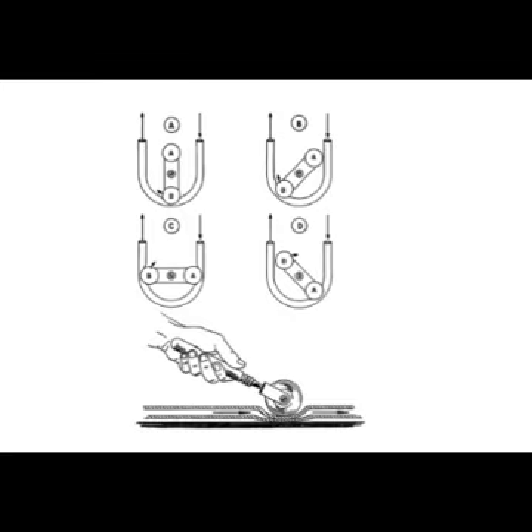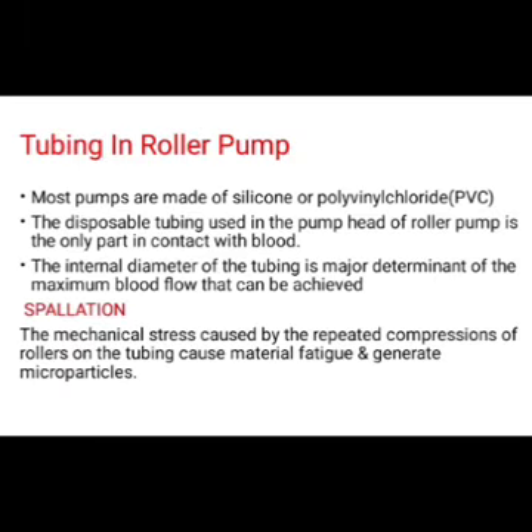Here is an image of a roller pump. Tubings used in roller pumps. Most pumps use tubings made of silicone or polyvinyl chloride. That disposable tubing used in the pump head of the roller pump is the only part in contact with the blood. The internal diameter of the tubing is the major determinant of the maximum blood flow that can be achieved. Spallation: the mechanical stress caused by the repeated compressions of rollers on the tubing causes material fatigue and generates microparticles.